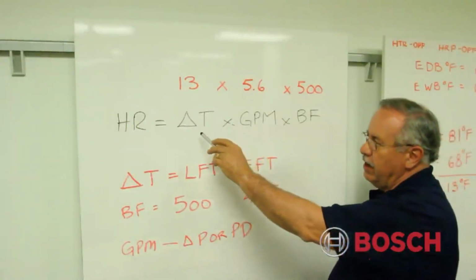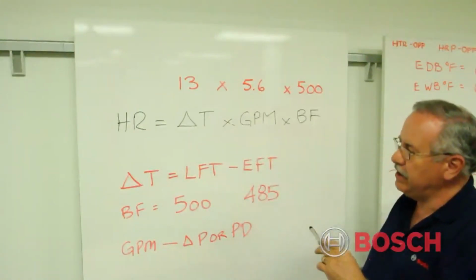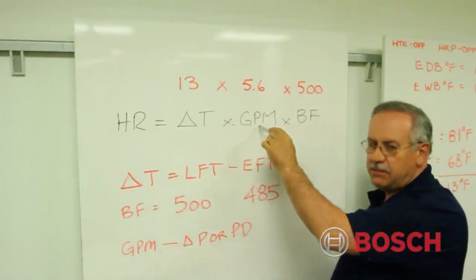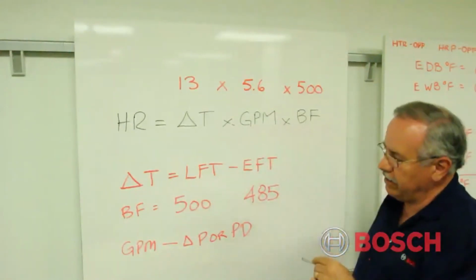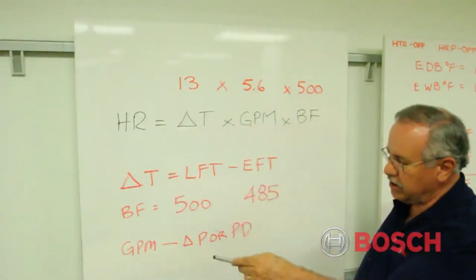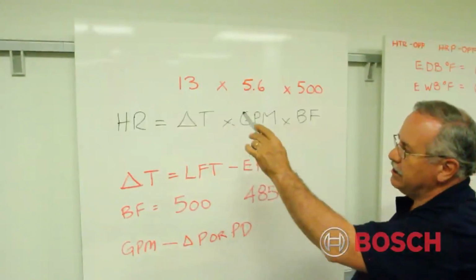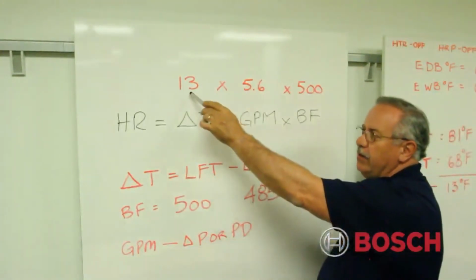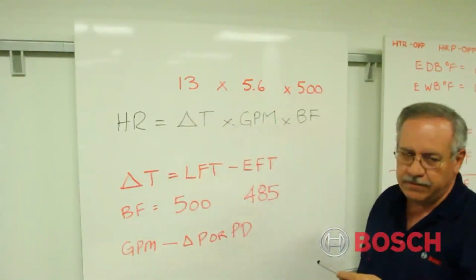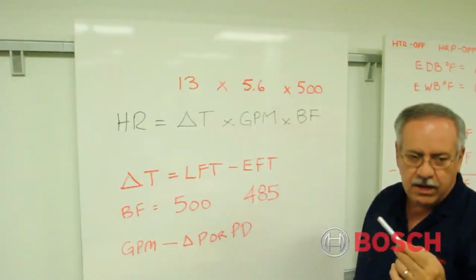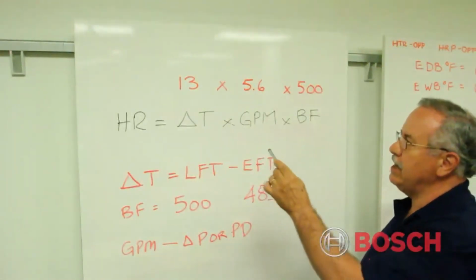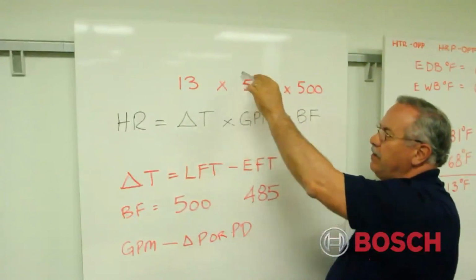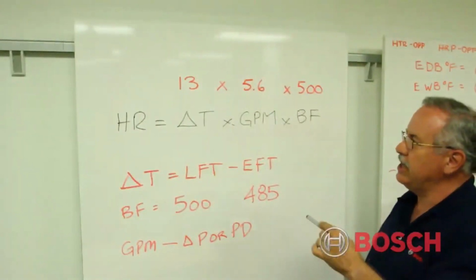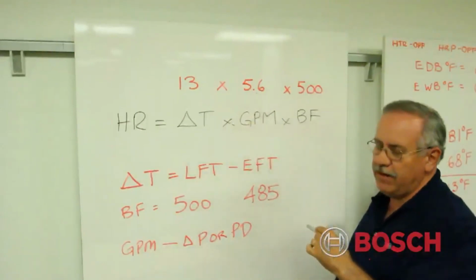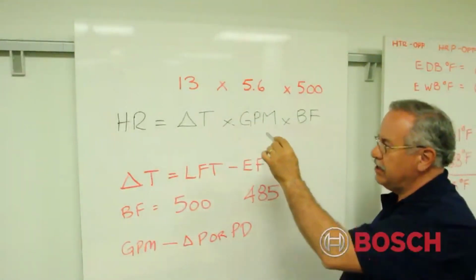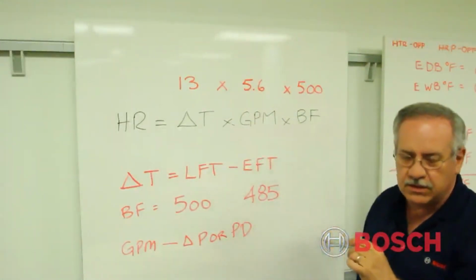cooling cycle, and we said that that would be factors of delta T across the heat exchanger times the GPM times the brine factor. Now what Mark determined from the live equipment was that he had approximately 13 degrees delta T, or temperature difference, from leaving to entering across the heat exchanger, rejecting heat to the earth. We determined from the product literature that 1 psig pressure drop was equivalent to about 5.6 gallons per minute. That's just what we need as one of the factors in our formula.